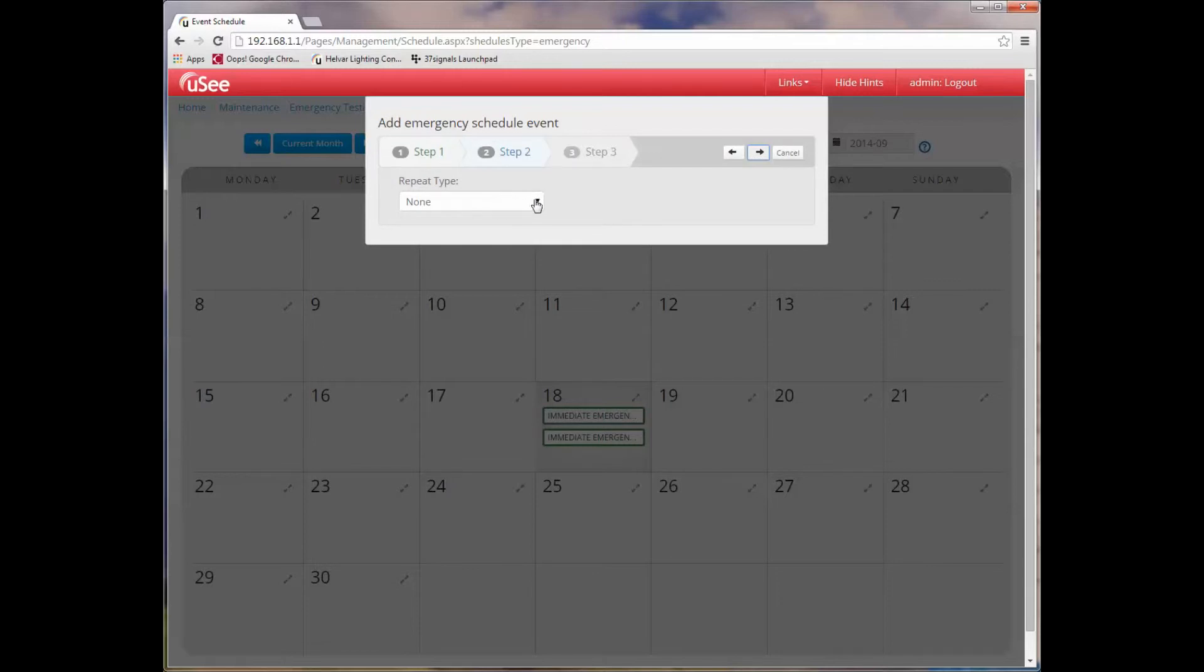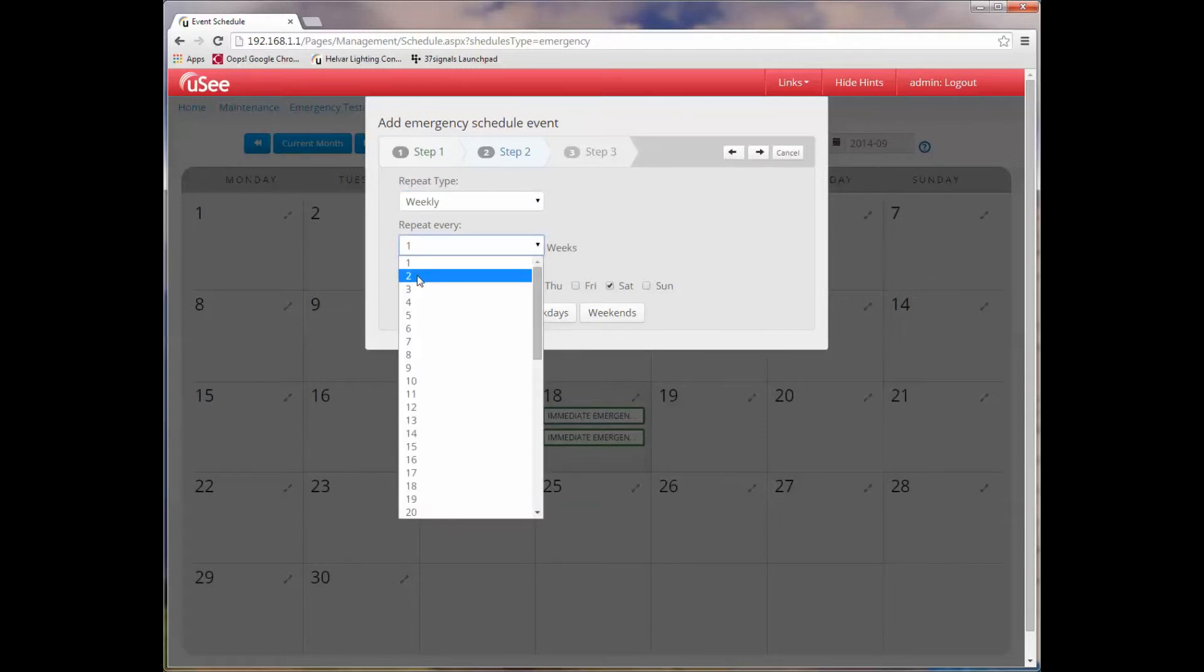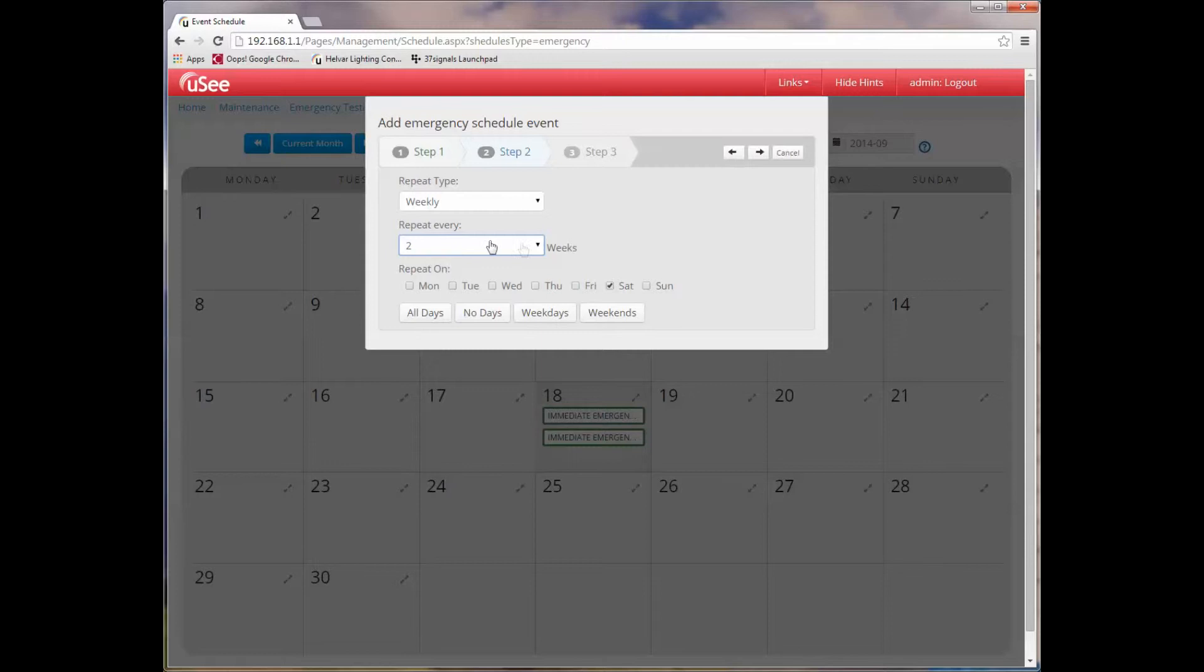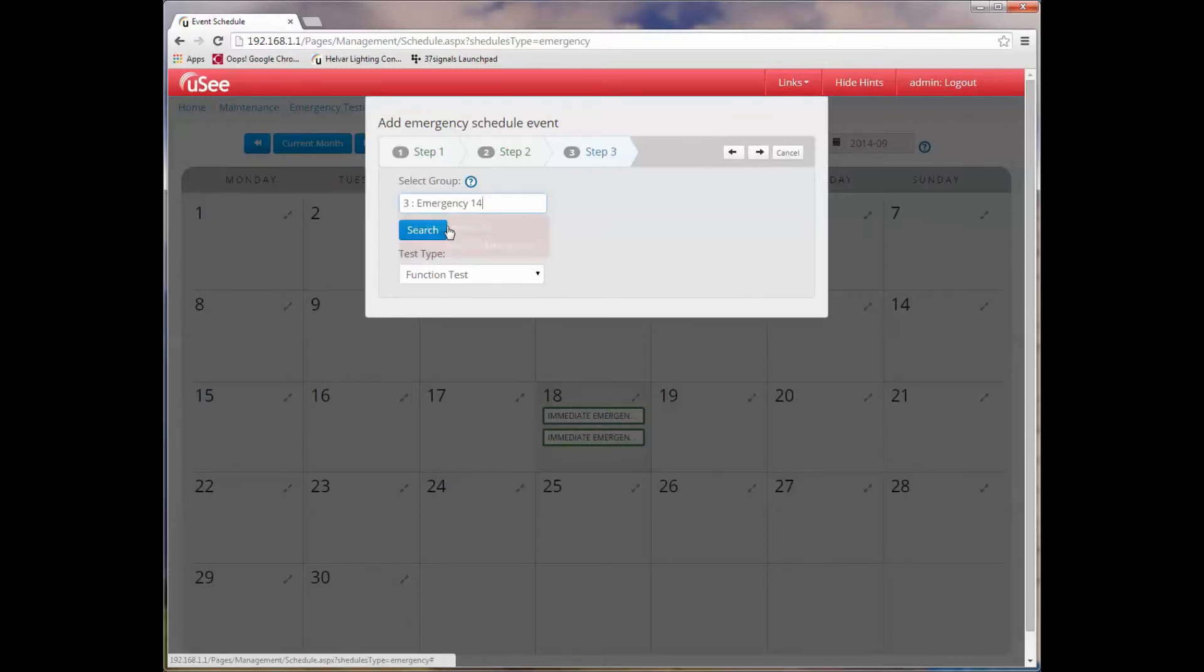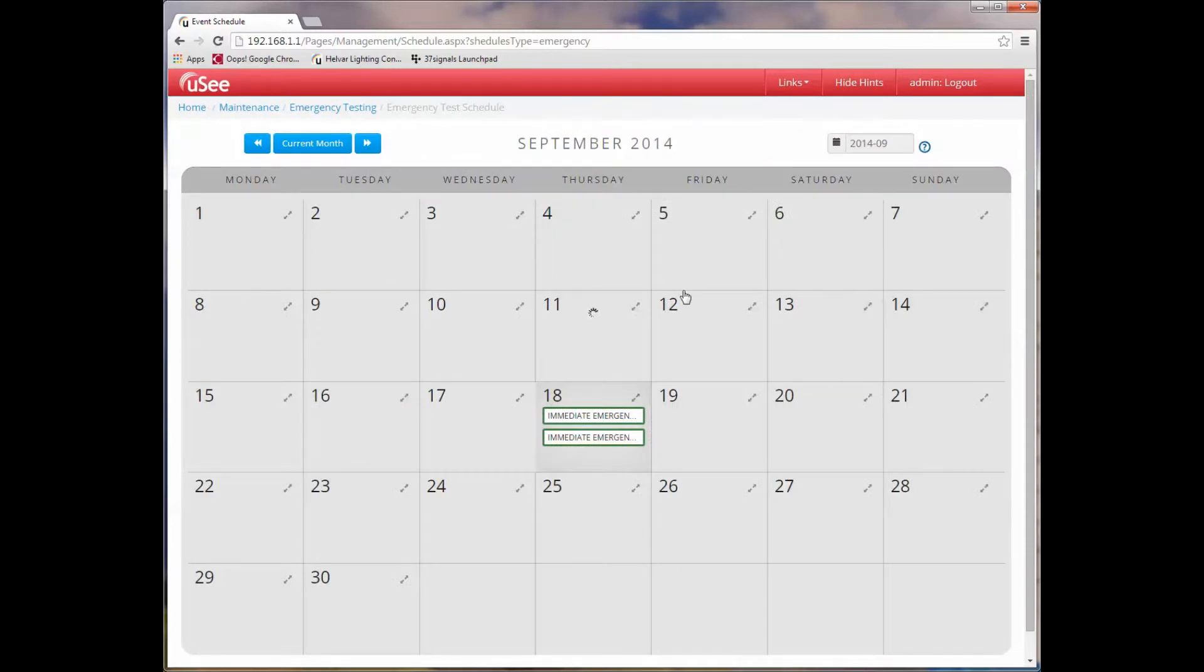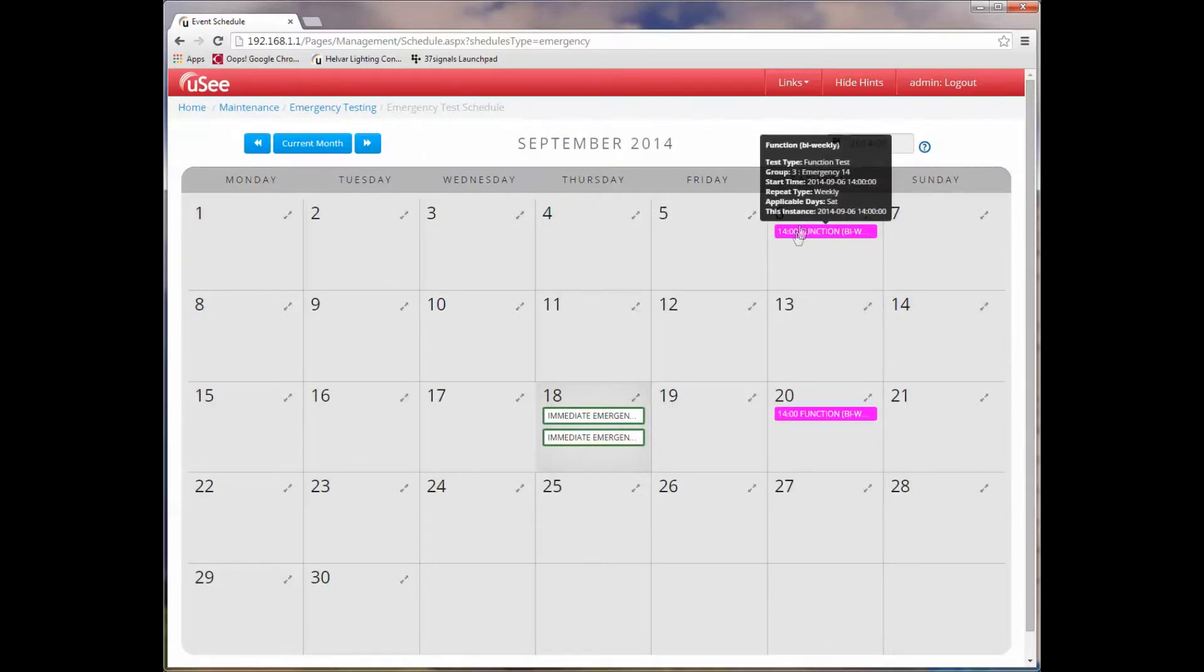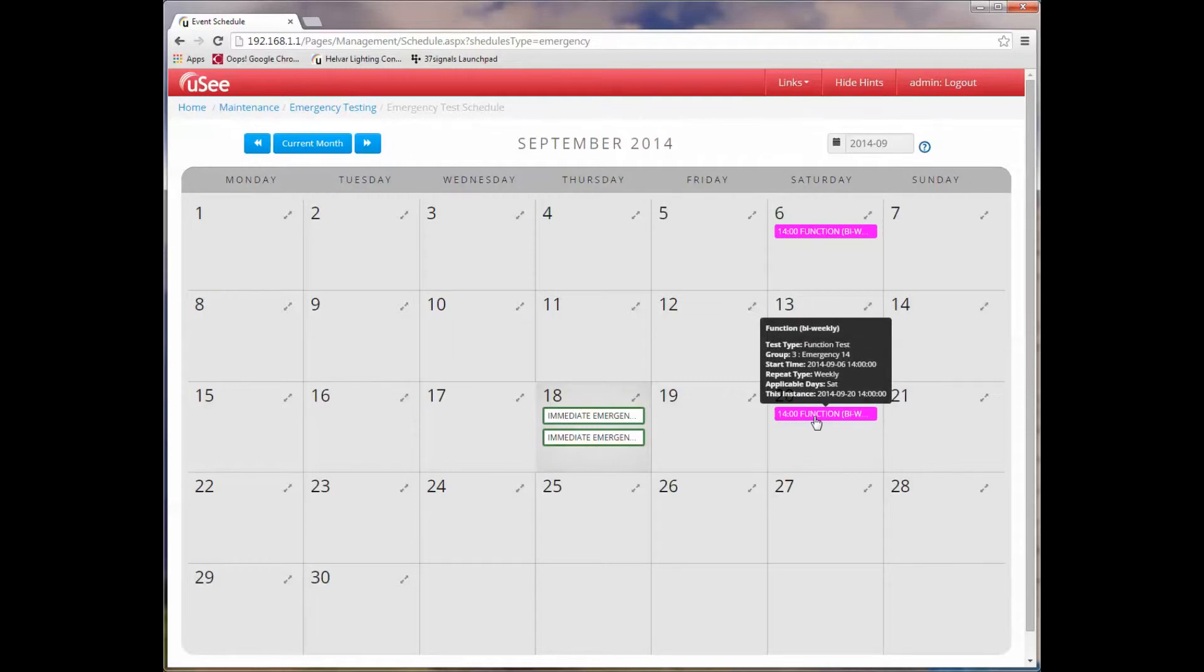It goes to the next step of the wizard. I do want to repeat this. I'm going to repeat this weekly, but I'm going to repeat it every other week. So we choose repeat every two weeks. I want to keep my day selection to be a Saturday. I'm going to choose my emergency group and I'll use the same method, EM. I'll select group number one, emergency 14. And as I said, we're going to do a function test. If I wanted a duration test, I could just select it from the dropdown and we'll do that in a while. The last step is to click the next button. And now you can see that the wizard finishes and the calendar view refreshes and shows us that we have now set up a function test which will happen every other week going forwards in time on a Saturday at two o'clock in the afternoon.